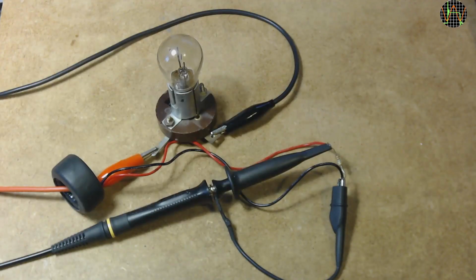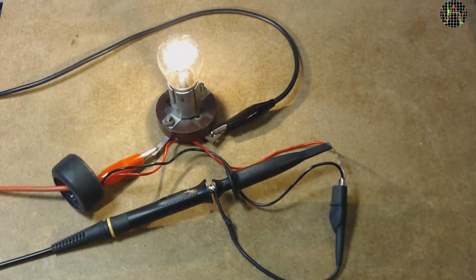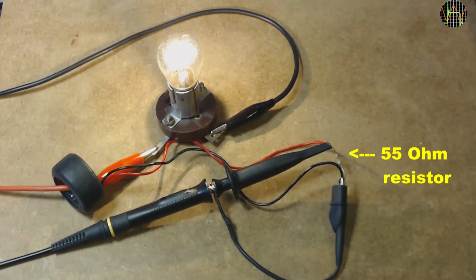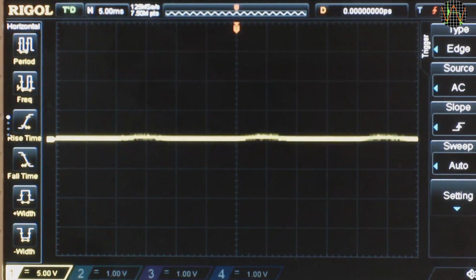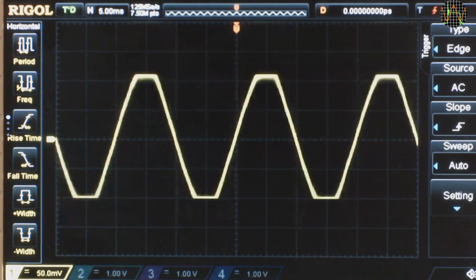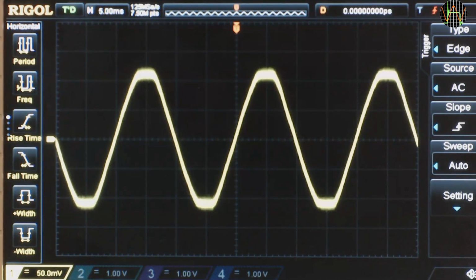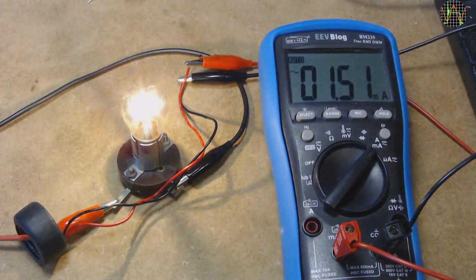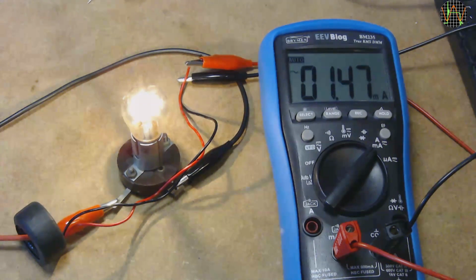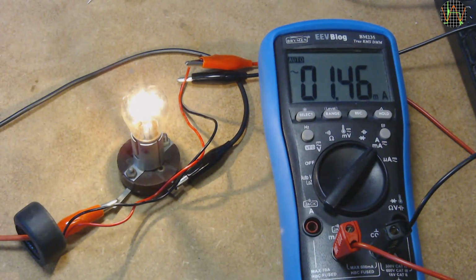To test what the signal looks like when the current transformer is properly loaded, I connected a 55 ohm resistor across the tip of the probe and the earth clip. Now the signal looks much more sinusoidal, like what you would expect, and the amplitude, which is effectively the voltage across the resistor, is just a bit above the 100 millivolt peak to peak. Using the BM235 in current mode, we can read the current to be 1.46 milliamps. Since the current through the light bulb is around 1.46 amps, this looks like the coil has 1000 windings, if you remember the formula for current transformers shown earlier.